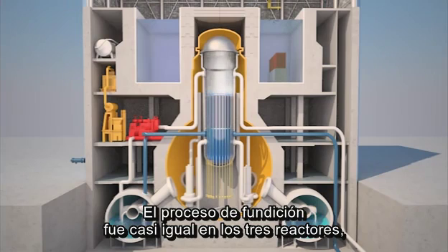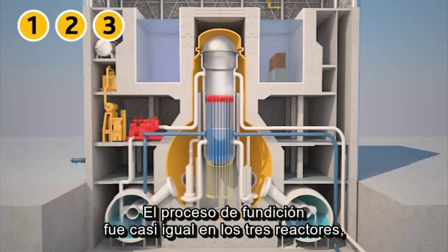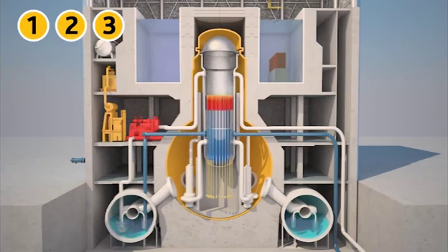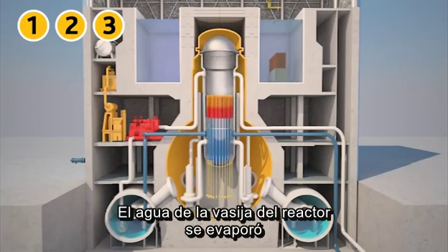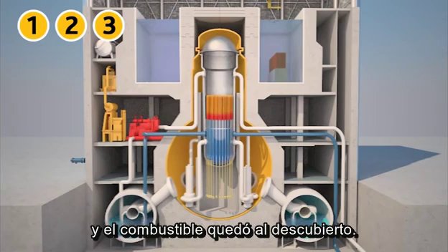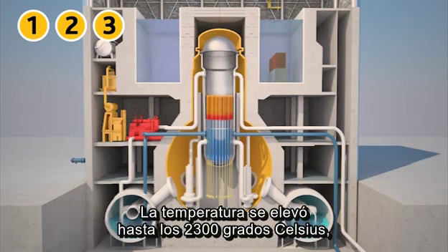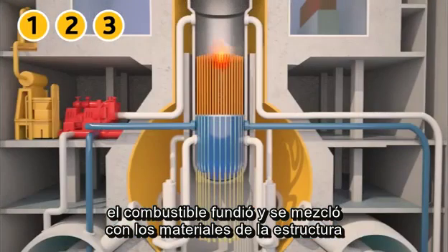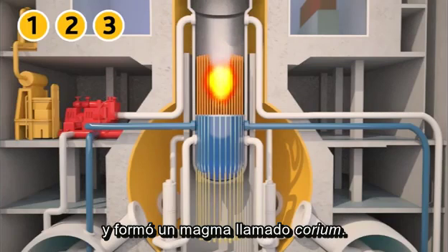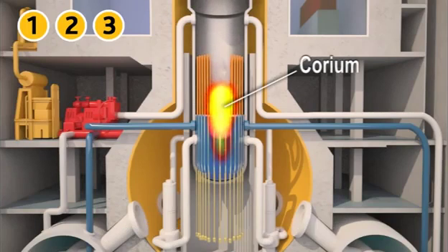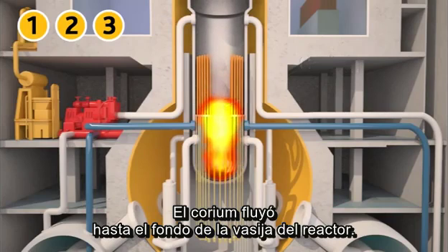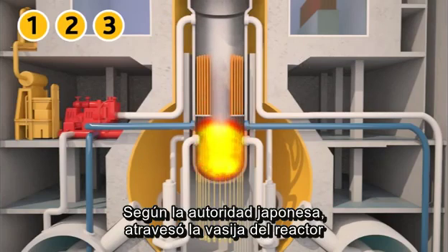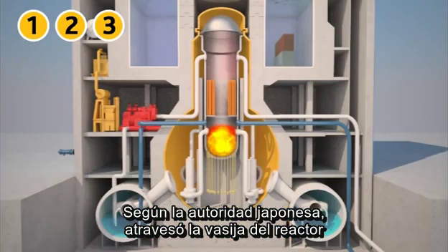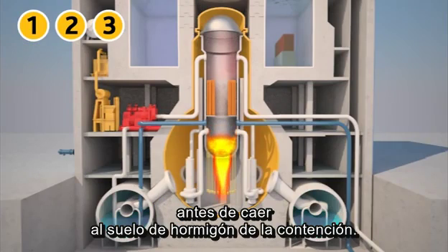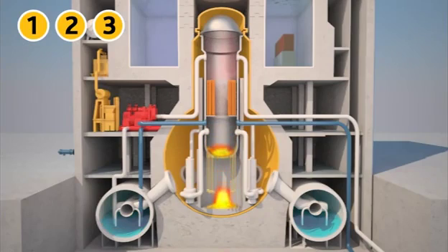The meltdown scenario is almost the same in all 3 reactors, only the dates change. The water in the reactor vessel evaporated. The fuel became uncovered. Heated up to a temperature of 2,300 degrees Celsius, the fuel melted and mixed with the materials from the structure to form a magma called corium. The corium flowed down to the bottom of the reactor vessel. According to Japanese officials, it pierced the reactor vessel before falling on the concrete basemat inside the containment.